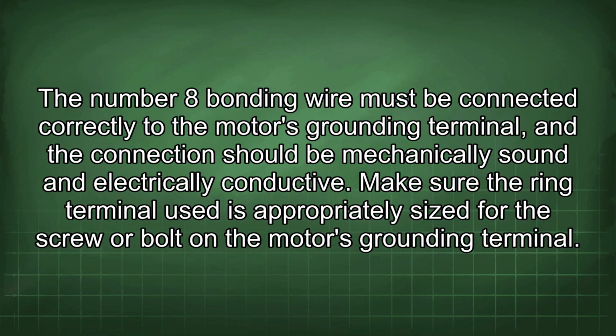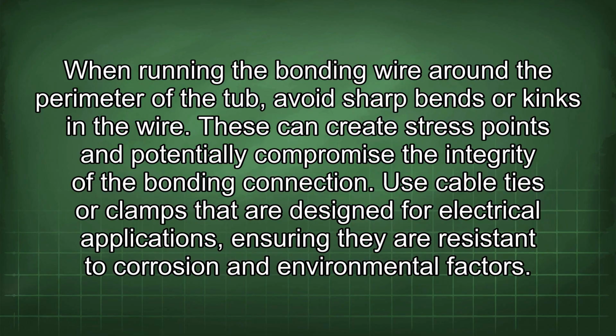The number 8 bonding wire must be connected correctly to the motor's grounding terminal, and the connection should be mechanically sound and electrically conductive. Make sure the ring terminal used is appropriately sized for the screw or bolt on the motor's grounding terminal. When running the bonding wire around the perimeter of the tub, avoid sharp bends or kinks in the wire. These can create stress points and potentially compromise the integrity of the bonding connection.